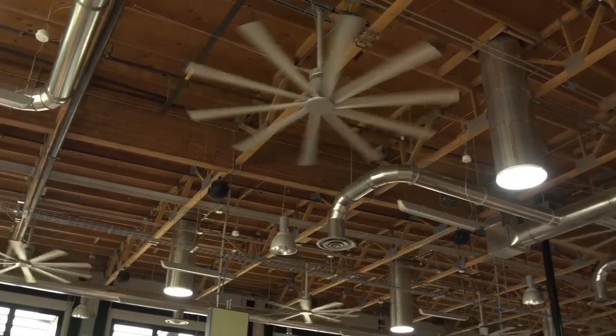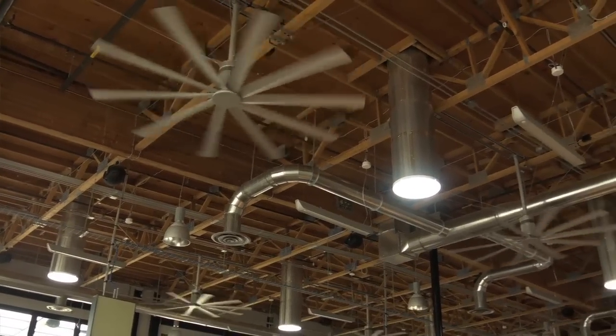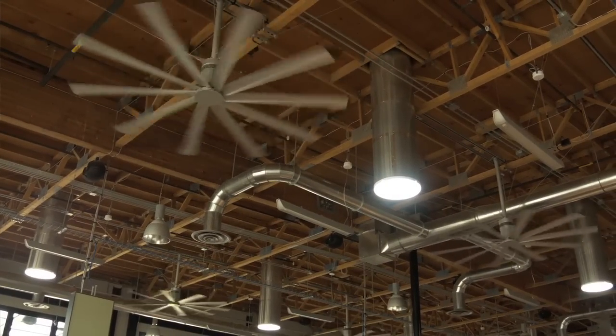Air speeds as low as 50 feet per minute can provide a perceived cooling effect. Generally in this kind of environment, in an office type space, we'd see air speeds maybe getting up to 150 to 200 feet per minute, which could give us a 5, maybe even a 6 degree cooling effect depending on conditions. The HVLS fans in this project have several different features that make them unique.